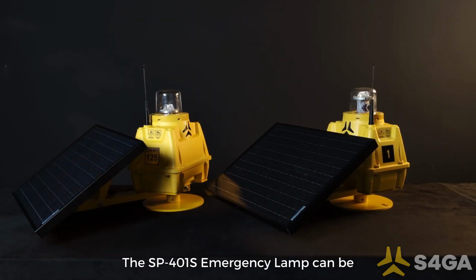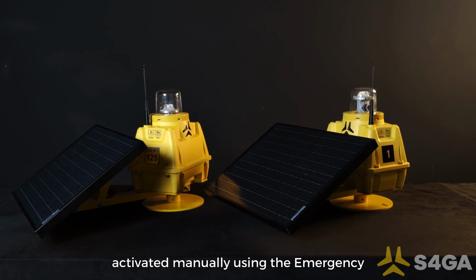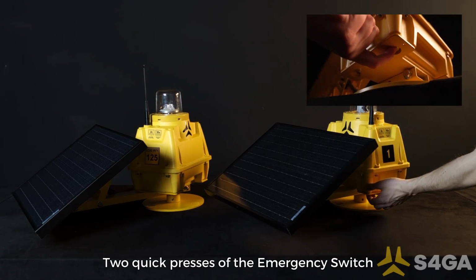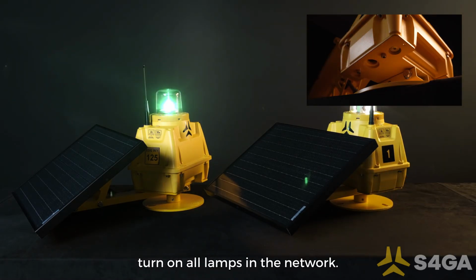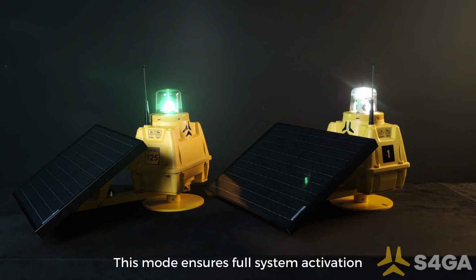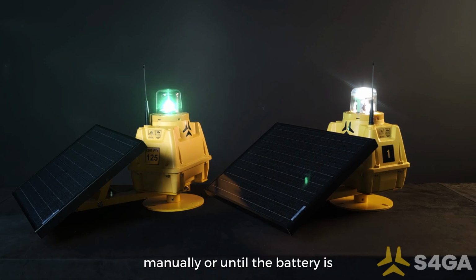The SP-401S emergency lamp can be activated manually using the emergency switch. 2 quick presses of the emergency switch turn on all lamps in the network. This mode ensures full system activation when remote control is unavailable. The lamp stays on until it is switched off manually or until the battery is discharged.